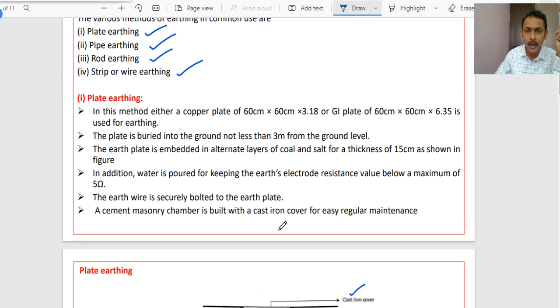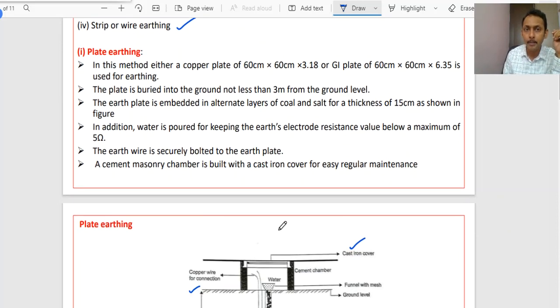Coming to its physical dimensions, while selecting plate earthing, the copper plate dimensions will be 60 by 60 by 3.18 centimeters. The GI (galvanized iron) plate will be 60 by 60 by 6.35 centimeters. The plate is buried in the ground not less than 3 meters from the ground level. You should not insert the plate within a distance of less than 3 meters; you should insert it at a depth below 3 meters. That precaution we have to take.